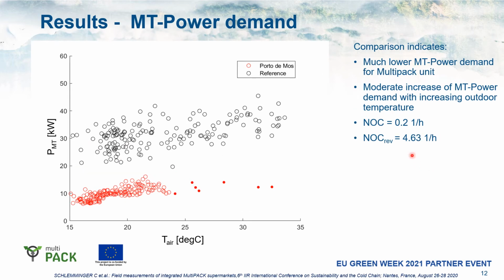Comparing the MT power demand, so the medium temperature refrigeration power demand, we see that the MultiPACK side has a substantially lower medium temperature power demand than the reference side, and it is only slightly increasing over the ambient temperature. We also see that the number of cycles for the MT is in the order of 0.2, meaning the compressors are almost all the time on. And for the reference side, the compressors are very frequently being switched on and off. So here the number of cycles is in the order of 4.6.